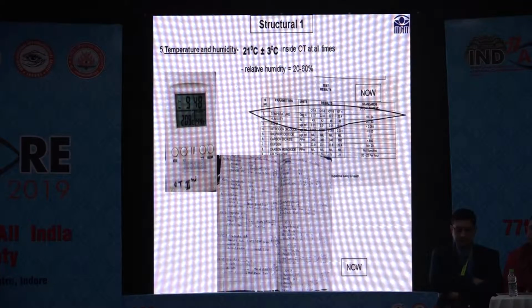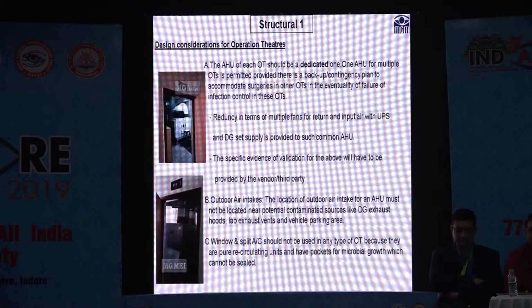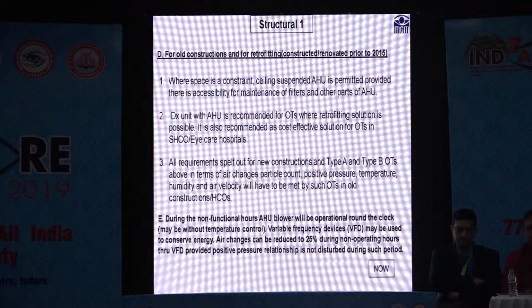We do air particulate counts, which are new to us, and we have started maintaining registers on a daily basis—this is new for us. Another requirement is that each OT must have its own AHU, and we should not have window or split AC units in any OT, because these are pure recirculating units with pockets for microbiological growth that cannot be sealed.